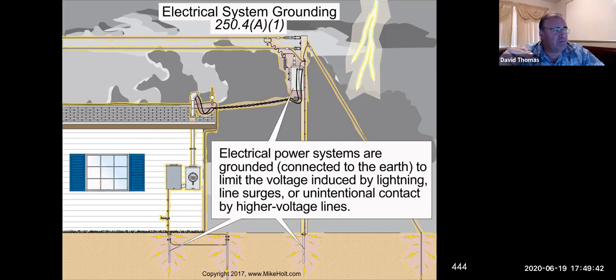So typically your telephone wires will be the bottom row, you know, Comcast, all the low voltage type systems will be down below. And then you'll have the medium voltage, like 120, 240 feeding houses. And then your high voltage will be 12,000 volts or something like that, 4160 on the top of the pole. So sometimes the higher voltage lines can actually contact the lower voltage power lines. And that's what they're saying in their unintentional contact with higher voltage lines.